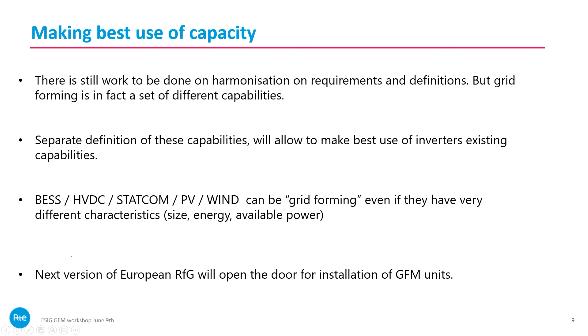Other work that has been done within RTE is the Ringo project. Ringo should usually be a grid following type of battery. We have three batteries used as virtual line, but as we had this battery and inverter on the grid, we ran a grid forming experiment where we black started a part of the grid with transformer and cables and 20 kV cables. We started a wind farm. We operated it in island for a few hours, and then we seamlessly connected back to the main grid.